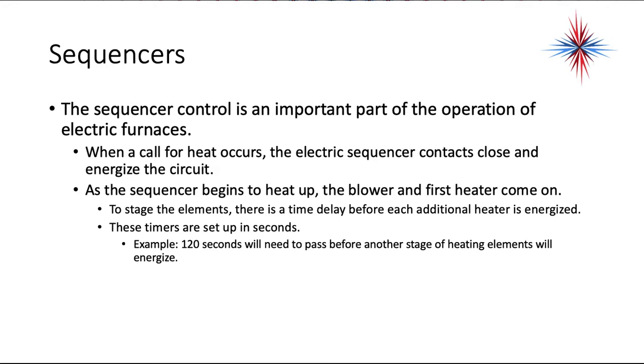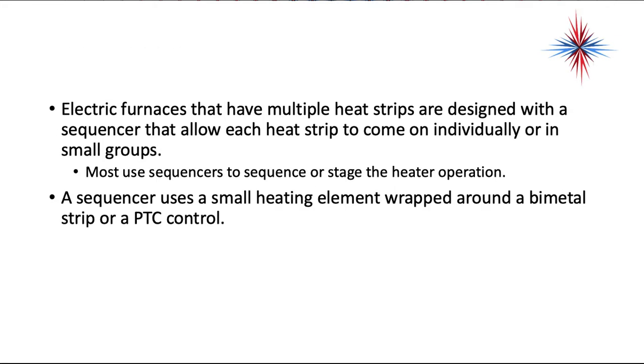In most furnaces, these are separated into 5 kW or 10 kW stages, depending on what your total heat is. So at the call for heat, the thermostat closes, and you would have your first 5 kW heat strip and the blower come on. Then 120 seconds would pass. That gives the current draw a chance to start on the first one and level out. Then the next one would come on, and so on.